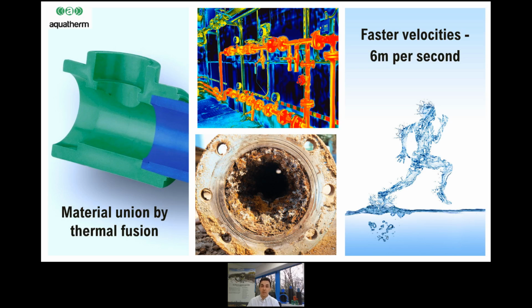Unlike the image of the pipework at the top centre of your screen, the thermal conductivity of fusiolen PP-R is 0.15 watts per metre Kelvin, and this offers a significantly higher degree of self-insulation compared to equivalent materials, leading to lower heat loss. The innovative fusiolen within Aquatherm pipes is made from a chemically inert material, which ensures the pipe is anti-corrosive, so you won't be seeing pipework images like the one on your screen. And as Aquatherm pipes are non-transparent, there is no risk of algae formation within the pipework.